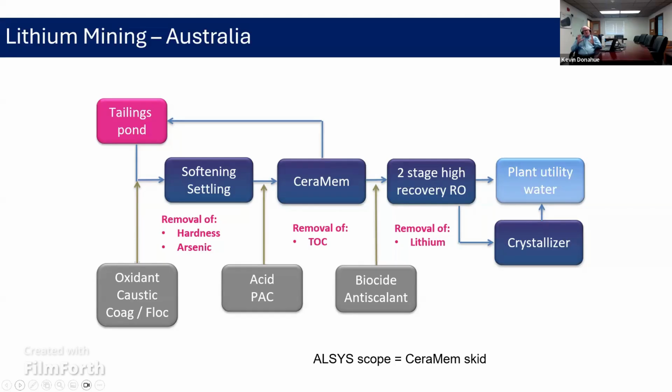And then the Ceramem permeate, in this case, we're adding some anti-scalant, and then it's going to an RO unit. Some people experienced with RO may know that the best quality feed, the lowest SDI you can give to an RO unit, would typically be from a UF system.